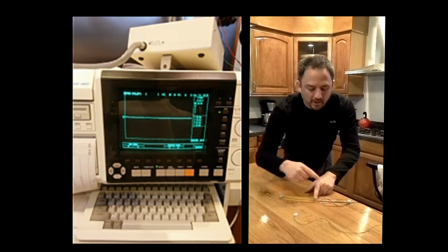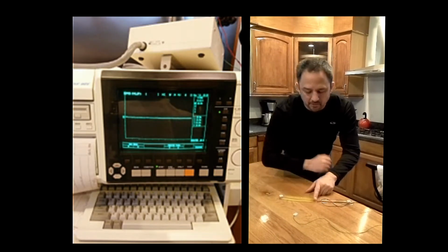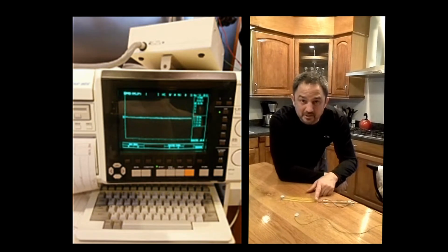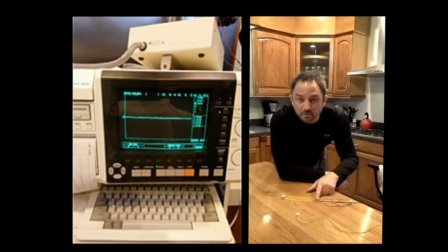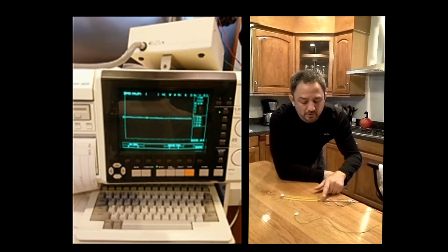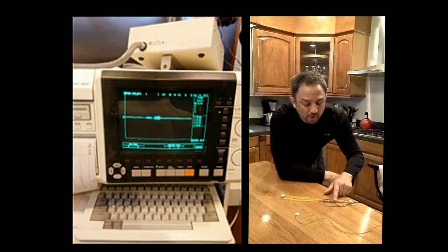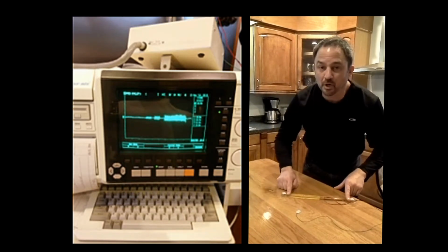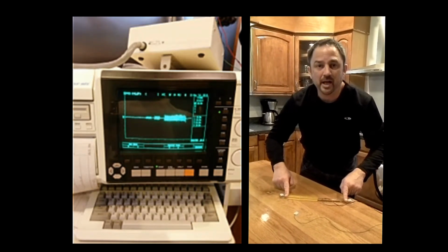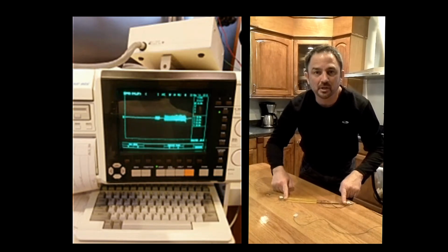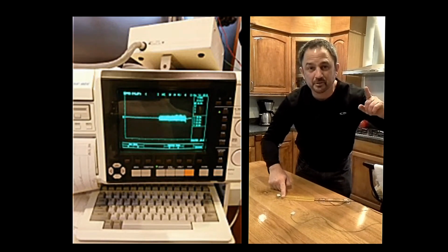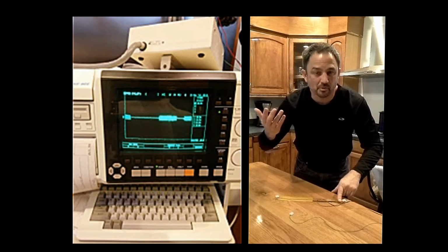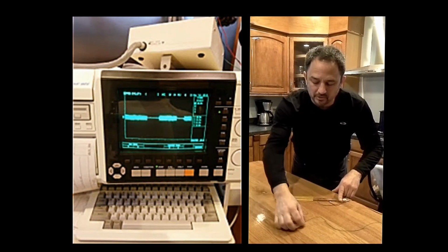If I touch in the middle, I'm equidistant between the anode and the cathode, and the amplifiers amplify the difference. So it's zero. The closer that I get to one or the other of the poles, the larger the noise signal amplified. If I touch both, I am back to being kind of in the middle, and it cancels. Lift, large noise, cancel. Lift, large noise. Let's leave it on large noise.